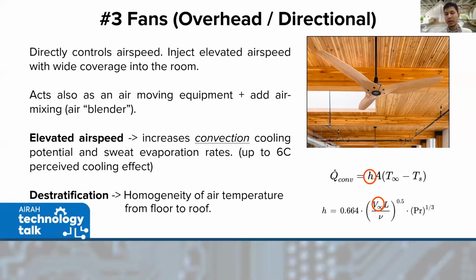For fans, we can perceive up to 6 degrees of cooling effect, and also destratification - mixing the air up gives homogeneity of air temperature from floor to roof. For heating applications this is important because hot air sits at the top and you actually want that hot air to be at the bottom where the occupants are. I've highlighted the convection coefficient with the airspeed here.